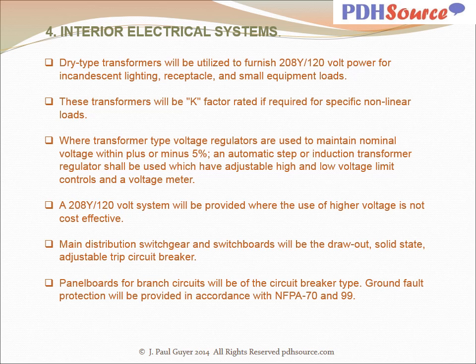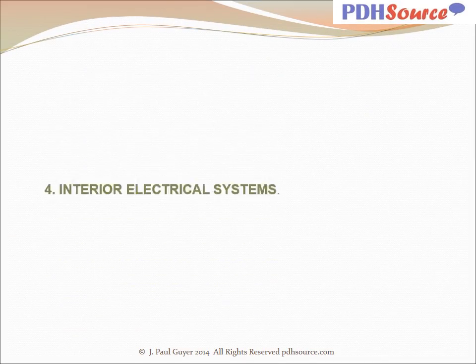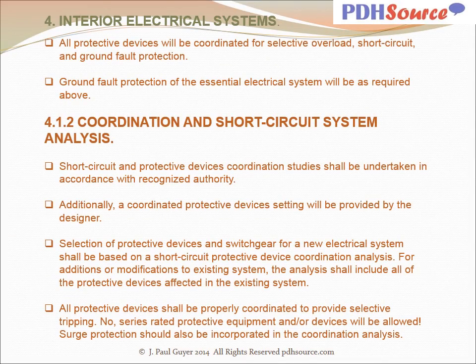Panel boards for branch circuits will be of the circuit breaker type. Ground fault protection will be provided in accordance with NFPA 70 and 99. All protective devices will be coordinated for selective overload, short circuit, and ground fault protection. Ground fault protection of the essential electrical system will be as required above. Short circuit and protective devices coordination studies shall be undertaken in accordance with recognized authority. Additionally, a coordinated protective devices setting will be provided by the designer.